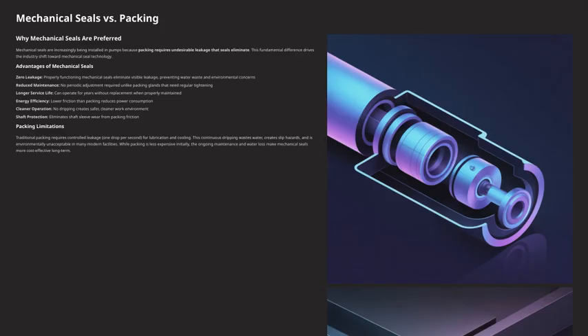Energy efficiency is another big plus. Mechanical seals generate less friction than packing, which means they consume less power. Plus, they keep operations cleaner. No dripping means a safer, tidier work environment. And finally, they protect the shaft from wear caused by the friction of packing, extending the life of the shaft and related components. Now, let's look at packing limitations. Traditional packing needs a controlled leak, usually about 1 drop per second, to keep the packing lubricated and cooled. But this constant dripping wastes water, creates slip hazards, and isn't environmentally acceptable, especially in modern facilities. While packing may be cheaper up front, the ongoing water loss and maintenance costs make mechanical seals more economical over time.